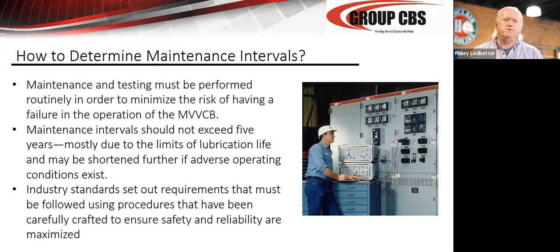So you need to block it closed or close the breaker if you're going to ship an interrupter, or you need to put some blocking material in it where the bellows isn't going to move if you ship a loose interrupter. So absolutely, shipping a vacuum breaker, if it's not one of the modern breakers that is splined. The new breakers have a spline in the moving contact assembly, and it adds rigidity, and you don't get the vibration and the frequency and the damage to the bellows. Was there something else?